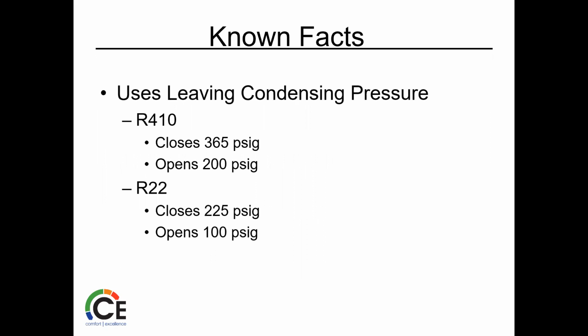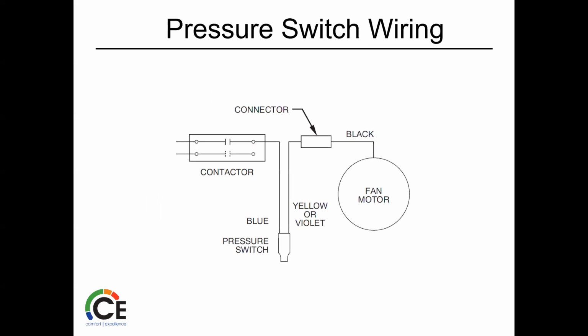If it's a 410A version, it opens at 200 and closes at 365. So it closes, brings the fans back on, and we start to drop temp down. Or 22 the same way, it just opens at 100, closes at 225. Wiring, again, you're just breaking that connection to the fan motor. We're taking that line voltage, instead of it going right to the contactor, one's going through the switch, the other's coming out, going to the fan.